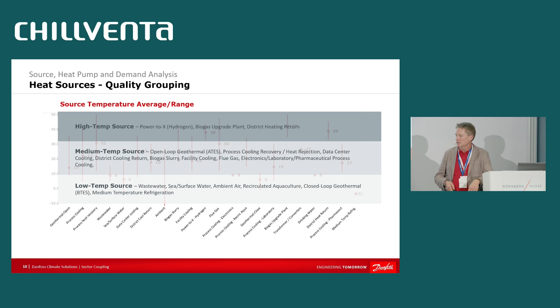You can also play with the system design. Coming from the cooling world myself—I spent 17 years in product planning for chillers, air handlers, and similar equipment—when I started working on integrated energy system designs, we quickly recognized that electrifying heating systems introduces a dynamic that's critical to how you design the system. Chiller engineers have for 25-plus years used series counterflow systems, an approach our centrifugal chiller team developed, which reverses the flow of a two-circuit system.